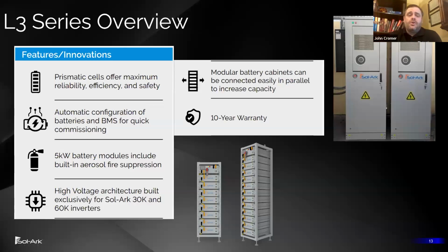Now, that said, our commercial product line is at the moment focused on light commercial or small to mid-sized commercial. And part of that is ease of installation. So we use 100 amp hour cell formats, and those are a little bit more expensive than what you'll find in containerized solutions, which might go with 200 amp hour or 300 amp hour cell formats, but they're batteries that your workers can actually pick up and move around. So much faster installation times.